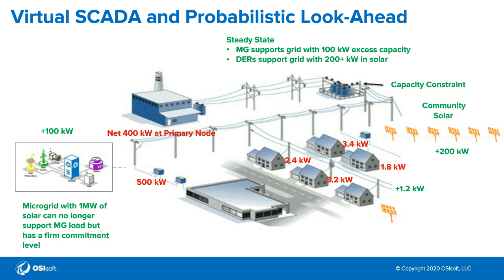If we look at this scenario in steady state, this might be a non-wires alternative scenario where there's a capacity constraint at a particular substation, and DER has been deployed downstream to help mitigate that. That makes operating this system more complex because you're dependent upon the operation of downstream assets to keep the system from overloading.